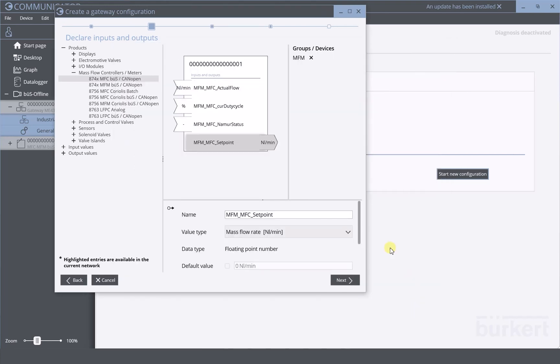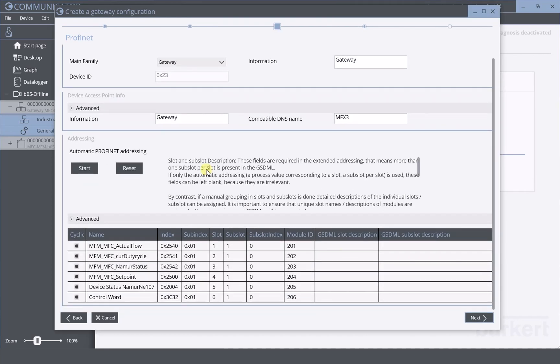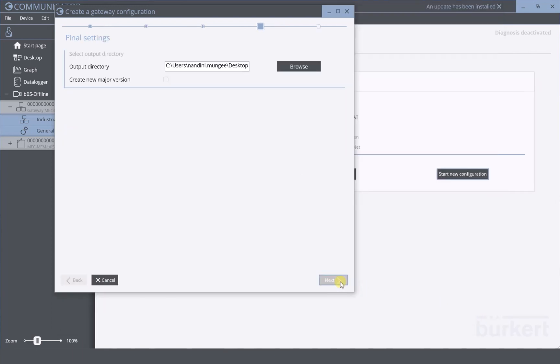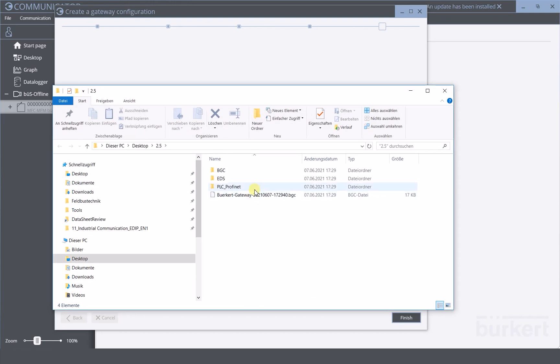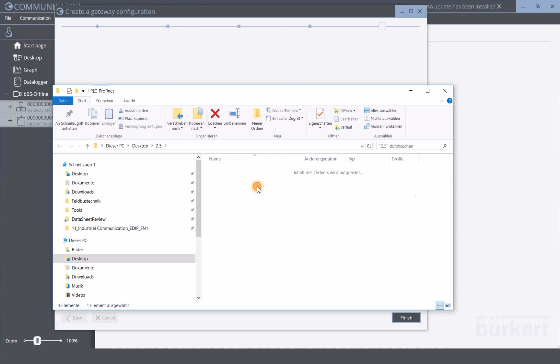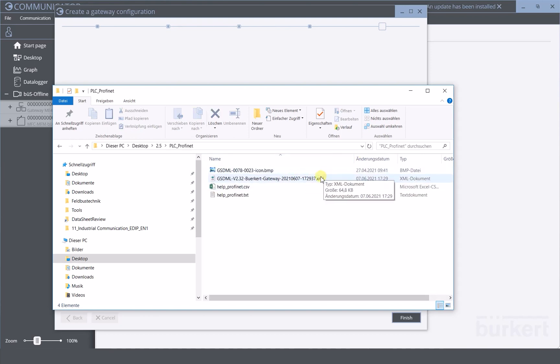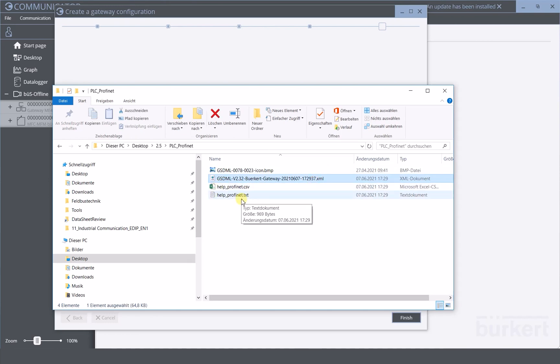Let's proceed to the next step. Once all the values have been selected for all the devices, here's an overview of all the values that are going to be transmitted to and from the PLC. The next step will be to save this configuration. Save it to any folder on your laptop and let's proceed. The configuration is saved, and the most important file for the customer is the PLC file. For Profinet, the GSDML file is created. There are also a few help files with all the details of the parameters.